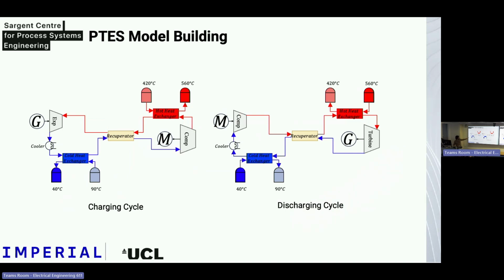As I said, while charging, the system operates as a heat pump. The working fluid goes into the compressor, reaches high temperature and pressure, exchanges heat with the hot side, goes through the recuperator, comes back, expands through the expander, then goes to the cold side receiving heat from that, and goes through the recuperator again, closing the cycle.